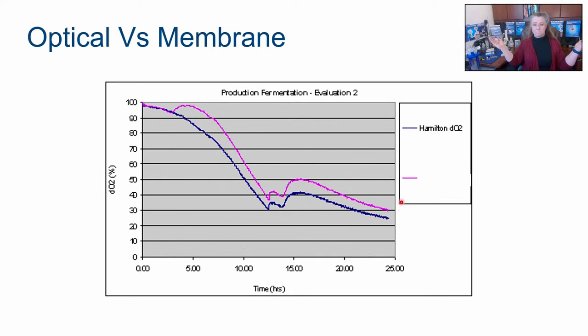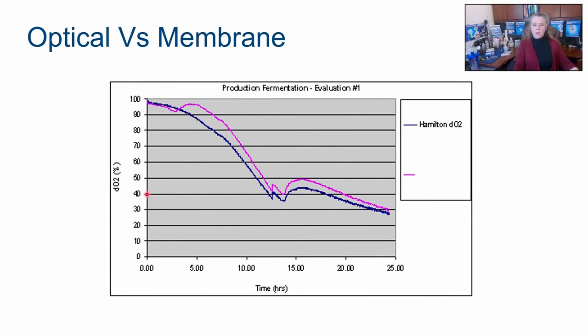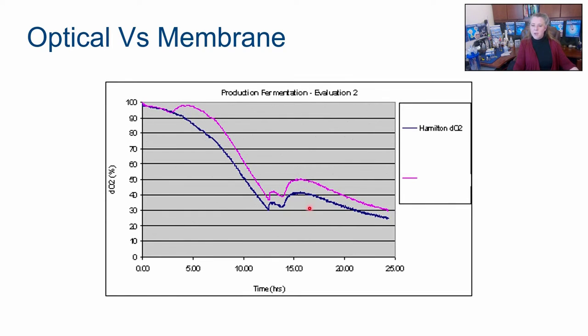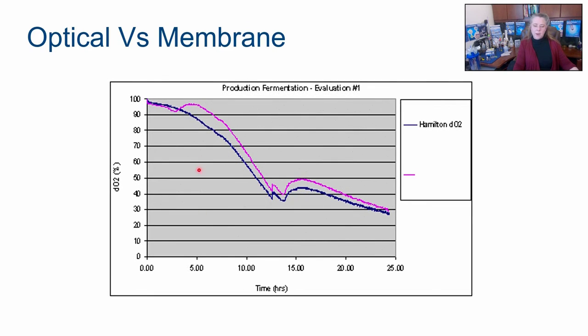And we told them, and they're like, I don't know if we believe you. I said, okay, cool. Run it again, only this time intentionally wait and open the valve and do the same thing. And so they did. And this time you'll notice last time there was about a 10% DO saturation. This one's around 40, this one's around 50. The second time they ran it, it changes again and it comes back. And the offset difference between these two is about 5%. That's a huge difference in oxygen saturation.